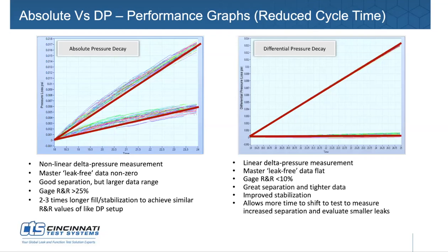And then comparing that to the right, a differential pressure decay, we can see a greater difference between those two slopes. And you see your non-leaking part has a lot more even slope in it. And the reason for that is using differential pressure decay, we're pressurizing our part and we're pressurizing a reference volume and comparing a pressure drop of your known tested part to this known non-leaking reference volume. And there's some thermal events that are nulling themselves out that you typically see as noise in the other sequence.